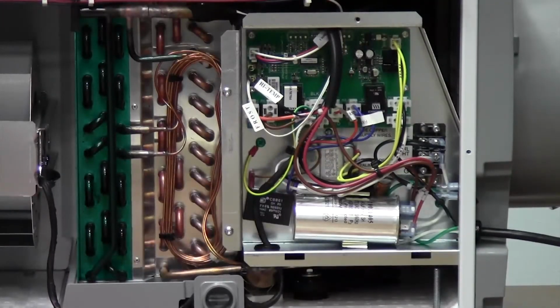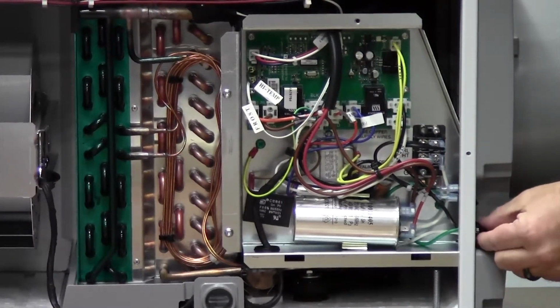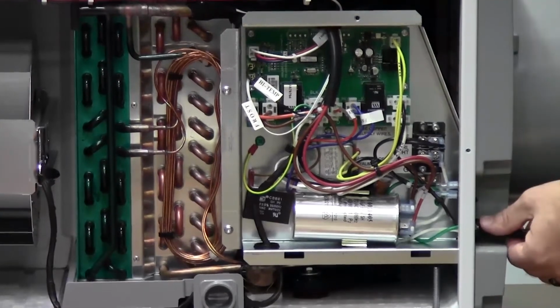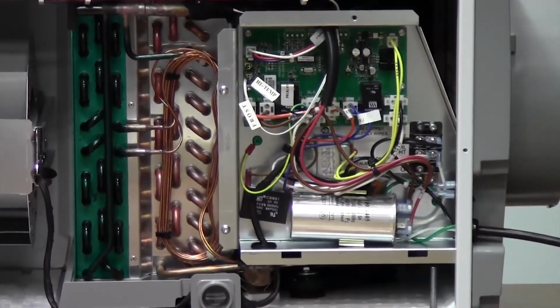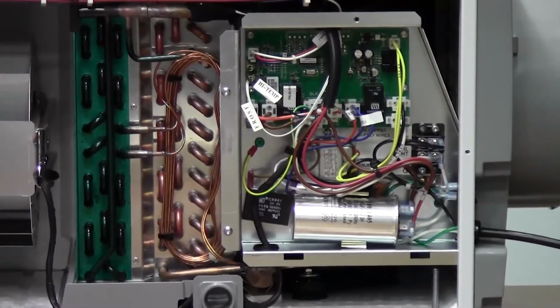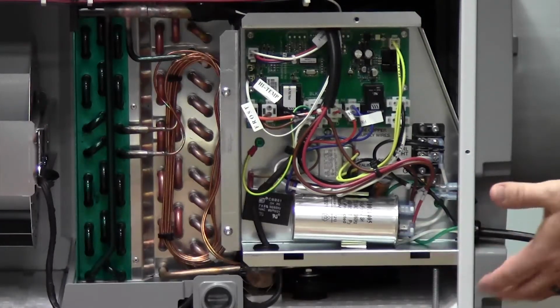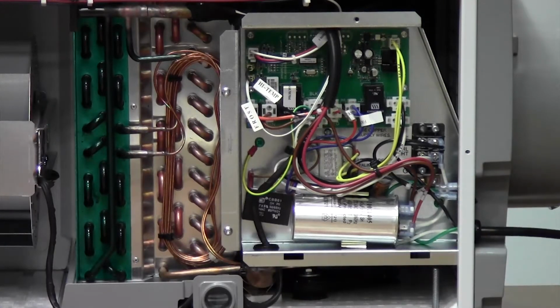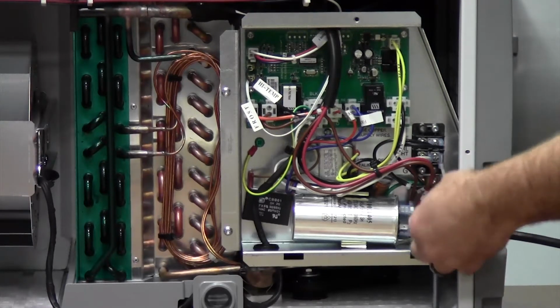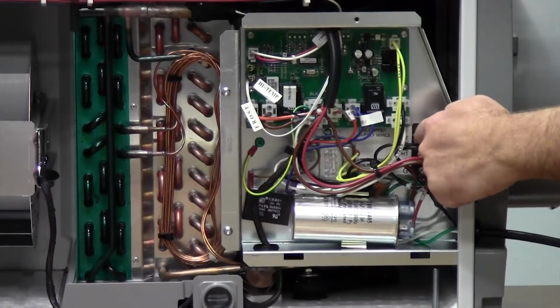So on the model 1830, you can use the cord that comes with it to power it up, or you can remove this cord and grommet and actually use conduit to hardwire it, for applications that require it, as some applications and codes require the unit be hardwired. This unit has a dual listing with UL and ETL that it can be hardwired or plugged in with a cord. So you can remove the cord and directly connect to the terminal blocks.